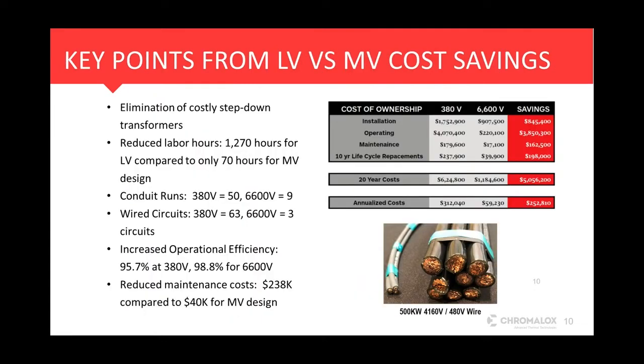Okay, so if we look at basically the summary of what electric solutions have to offer between the low voltage and the medium voltage, again, because you don't need to step down that voltage, you don't need the transformer. We talked about the labor involved in the mechanical parts with the conduit and the wires. And then, of course, because you have less wire, you have fewer of those I²R losses through the wire. And that's where you see that increase from about 96% up to 99% efficiency on the operational side. And because you're dealing with less wire and fewer connection points, that's drastically fewer components to manage and maintain. So when you look at the whole picture, you can see that the medium voltage systems become very efficient in terms of your commercial costs and your investment.